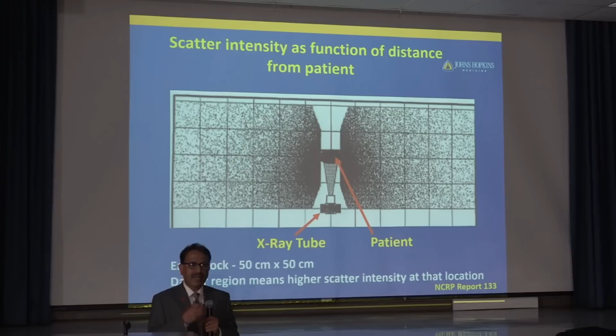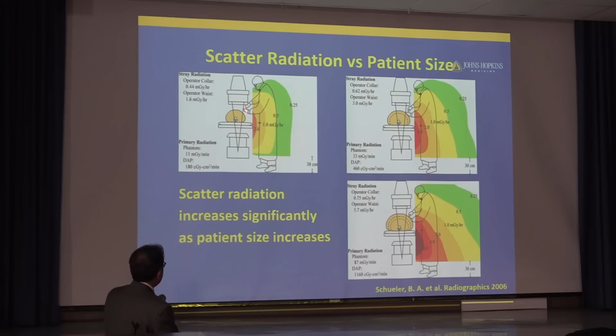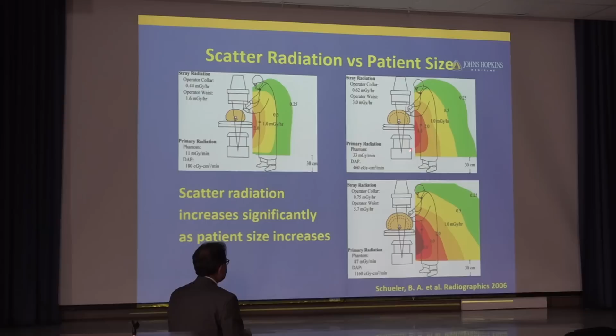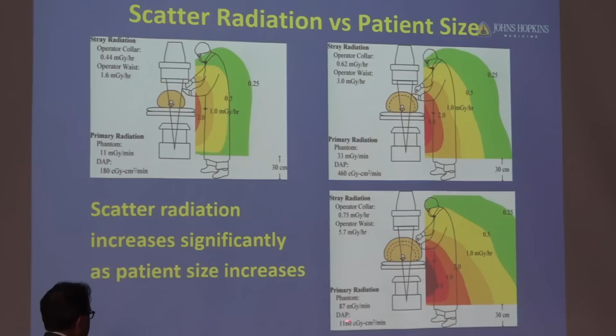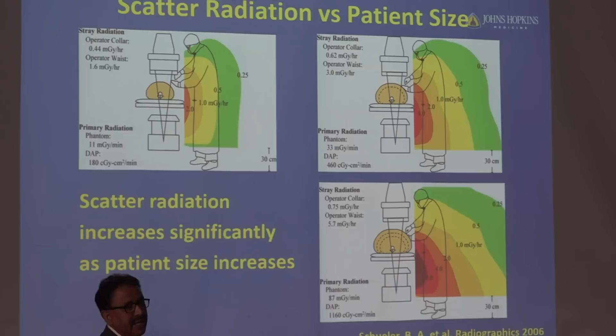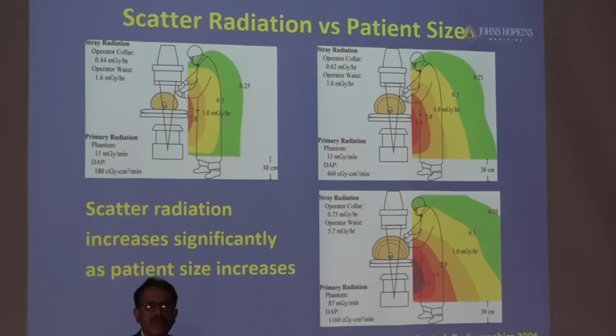And here's one diagram trying to show the impact of patient dose on scatter radiation. On an average size patient, I want to draw your attention to the numbers. I don't expect you to remember the units, but let's say it's 11 milligray per minute. The patient requires 11 milligray per minute. The scatter radiation is about 1 milligray per hour. Usually scatter radiation is measured in hours. If the patient size increases slightly, the system automatically generates more radiation. Because of that, the patient dose now is 33 milligray per minute. That's 3 times more dose. And the scatter radiation correspondingly increases. If the patient is extremely obese, it's about 8 times more dose compared to the average size, and correspondingly the scatter radiation also increases. So the rule of thumb is that scatter radiation increases significantly with the increase of patient size.